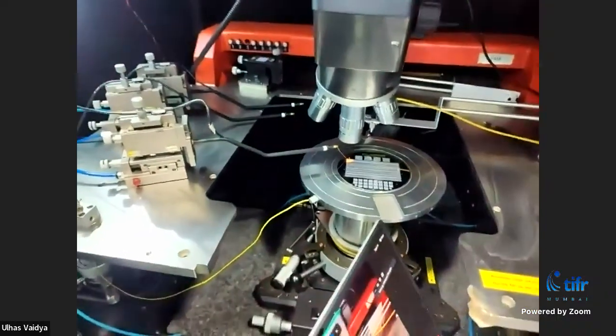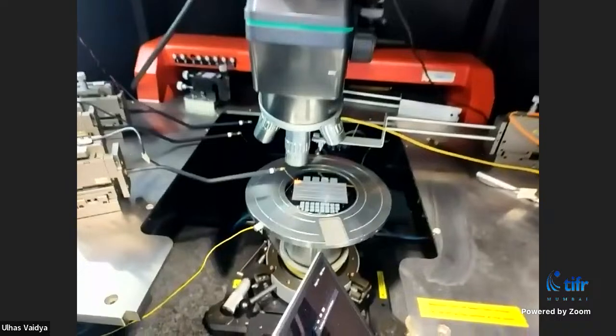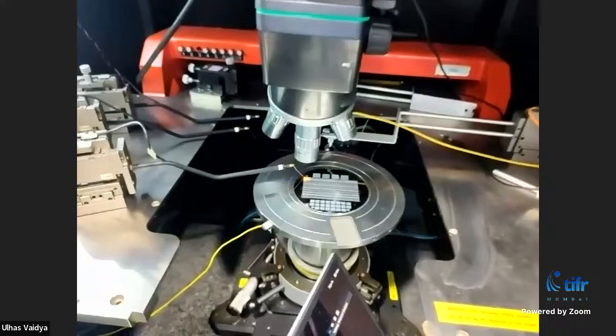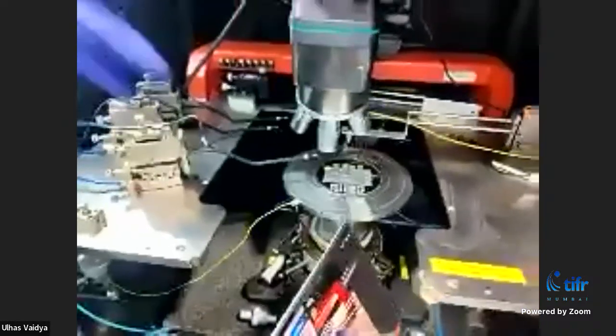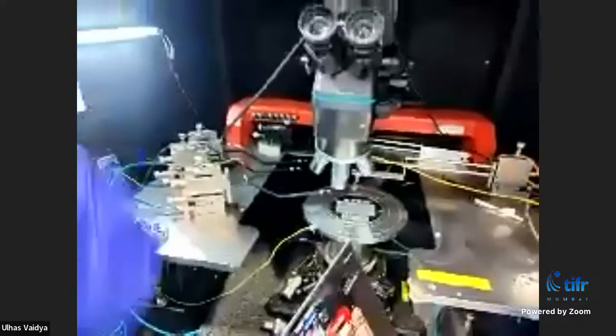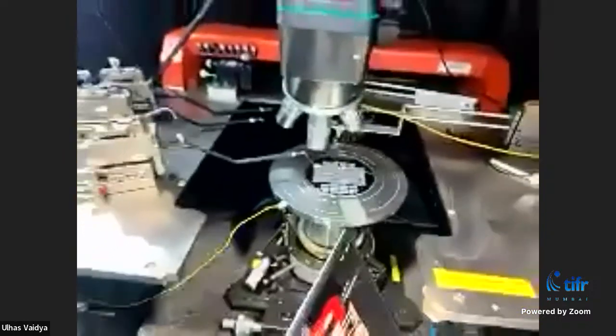Why is the environment dark? Normally we are measuring in microamps, sometimes even nanoamps, because the strip current is very, very small. Light also introduces some current, so to avoid environmental leakage current being added to the detector, we close it off from the environment and then measure. Is it electrostatically shielded? Not electrostatically, it's only for light. With light you can see an increase in the leakage current.